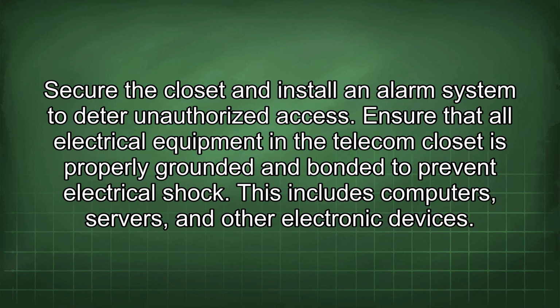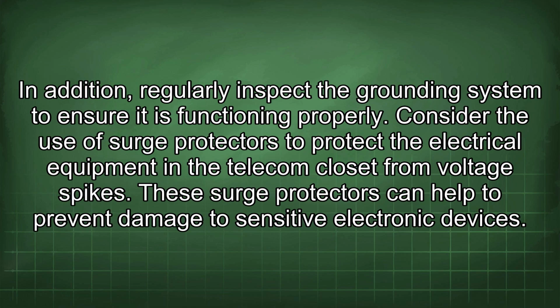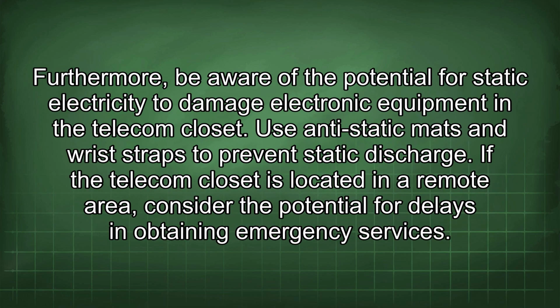Ensure that all electrical equipment in the telecom closet is properly grounded and bonded to prevent electrical shock. This includes computers, servers, and other electronic devices. In addition, regularly inspect the grounding system to ensure it is functioning properly. Consider the use of surge protectors to protect the electrical equipment in a telecom closet from voltage spikes. These surge protectors can help to prevent damage to sensitive electronic devices. Furthermore, be aware of the potential for static electricity to damage electronic equipment in the telecom closet. Use anti-static mats and wrist straps to prevent static discharge.